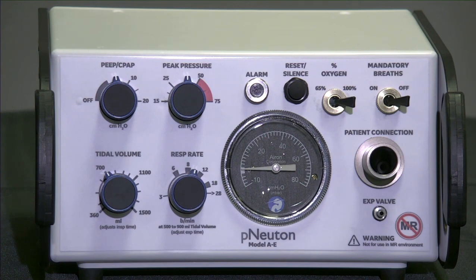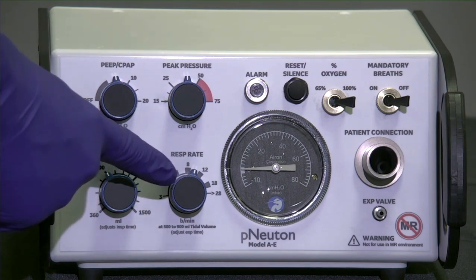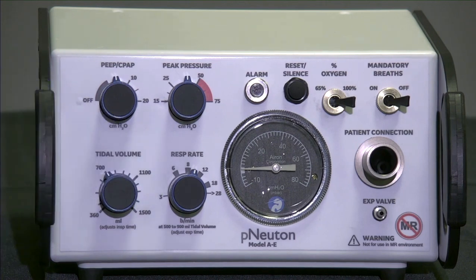Patient mandatory breath rate control. The respiratory rate control has a range of 3 to greater than 28 breaths per minute. The control has a wider range at the lower respiratory rates to provide better control for slower IMV rates. Patient respiratory rate should always be monitored to ensure adequate ventilation.